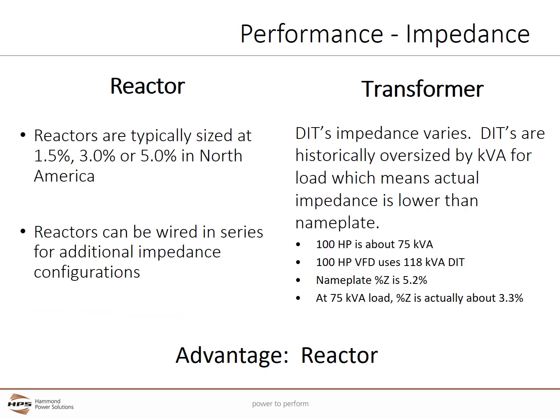Impedance performance. Impedance is an important consideration. The higher the impedance, the better the harmonic current mitigation. Reactors can be selected in 1.5, 3, or 5% configurations and can be wired in series for additional impedance configurations. DIT's impedance falls within a range of 3 to 6%. If a user wants a specific or minimum impedance, a custom and more expensive DIT may need to be sourced.